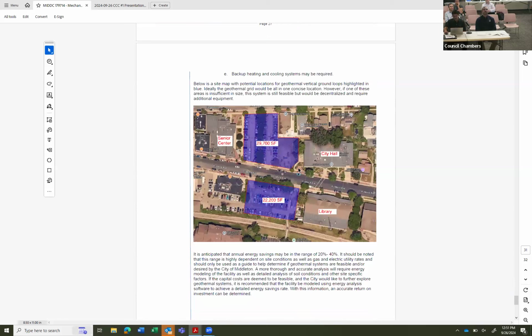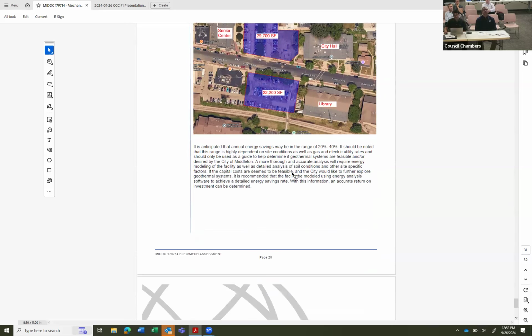And finally, down here, I just have a map showing potential areas: the parking lot between City Hall and Senior Center and the parking lot for the library could be potential areas for the geothermal fields. This is the approximate square footage of those, and it is in line with a typical system of that size. So potentially we could utilize the parking lot in between City Hall and Senior Center for the whole geothermal system. We might need to use both of these areas, but as I said before, further investigation would need to be done to determine those exact requirements.